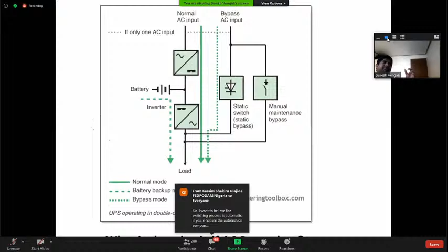So I can run my unit with float charging. But if you feel it may lose power immediately again, you need to keep your battery ready - then you may switch to the equalization press button and change your charger into equalization mode to quickly complete the charging. So the mode of operation is up to the operator's view, it is not mandatory.